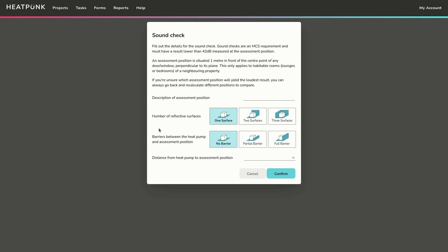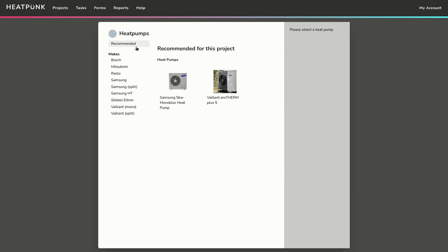I'm happy with the building, so I'll go to the heat pump section. The first thing it asks is the sound check: the distance to a neighbour's window or door, and the number of reflective surfaces for the heat pump. If it's on the ground against the property that's two surfaces; in a corner with two walls and a floor that's three; out in the garden on the ground that's one. You also specify whether there's a barrier, and the distance from the proposed heat pump location to the neighbour's window or door.